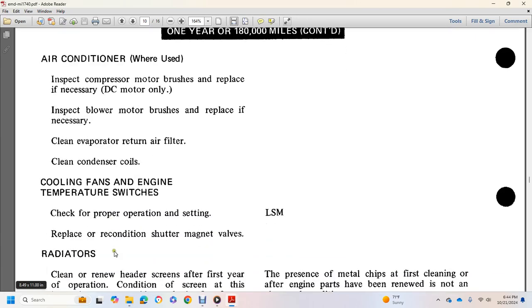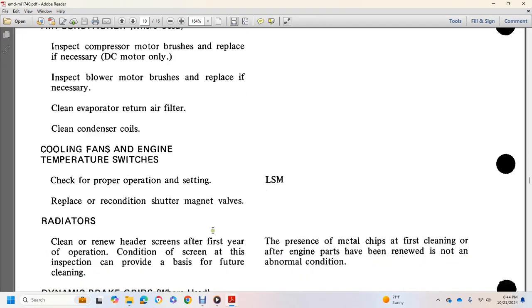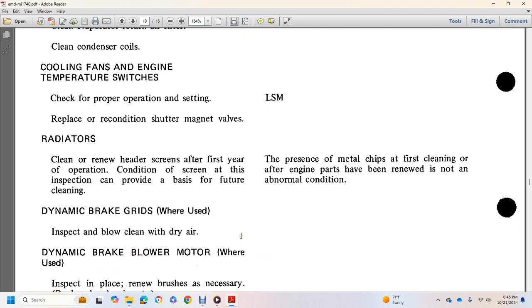coil, cooling fans, engine. Check proper operation and setting, replace or recondition shutter magnet valves. Radiators: clean, renew header screens after first year of operation, condition screen. Of this inspection, each provides a basis for future cleaning. The presence of metal chips at the first cleaning after engine parts have been renewed is not an abnormal condition.